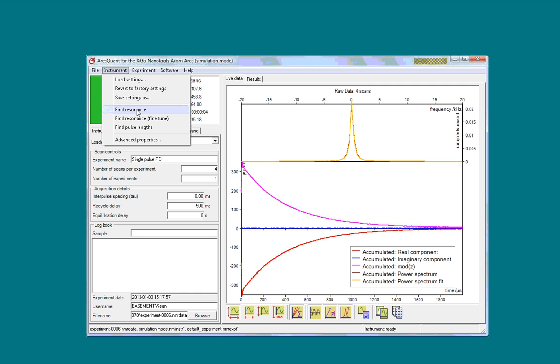Specifically, you can be up to 100 kilohertz away from resonance on either side, either in the positive or negative side, either less than the actual resonant frequency or greater than the resonant frequency, and still be able to determine the resonant frequency. This fine tune only works over a relatively narrow band, about 35 kilohertz, either plus or minus from the actual resonant frequency.